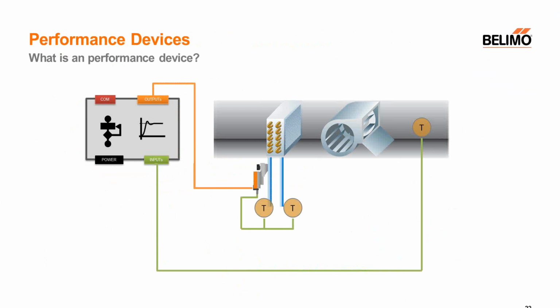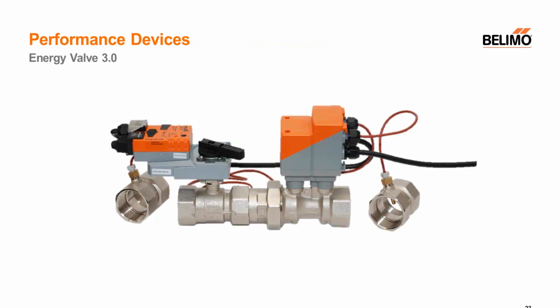From the perspective of this controller, it's the same, right? It's still the same PID loop looking at the same temperature and set point, trying to maintain temperature. But we've added some sensing and some logic in that device to make the process work better, to make the process smarter. And then it's logical that we want to communicate with this actuator, because now it has some data associated with it. It has these supply and return water temperatures, which are good for diagnostics. And it's just good data. So you want to be able to suck that out, and therefore we add communication. So that's a performance device.